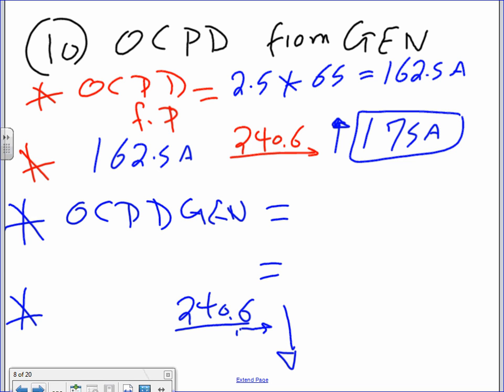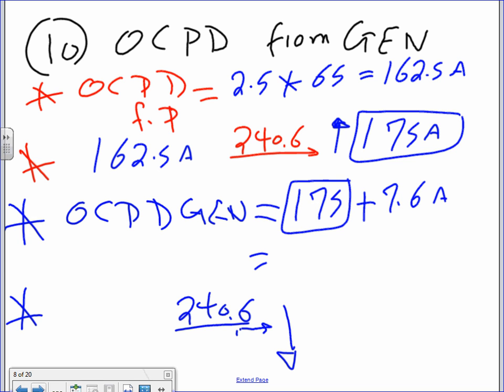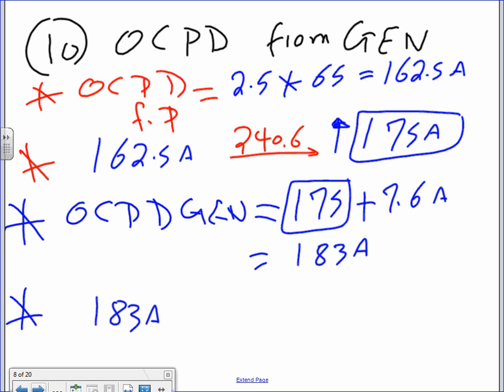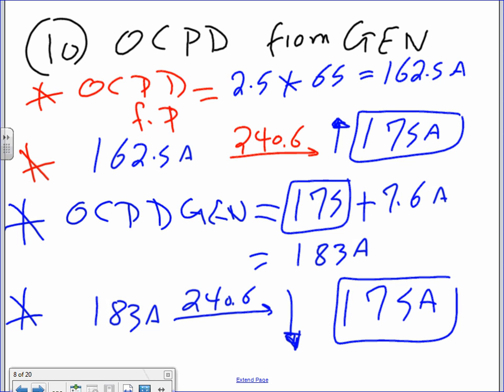Then, overcurrent protection device, guys, from the generator, the way you need to do it, you take the 175 amp that we just got. If you look at 7.6 amp, what's the 7.6 amp? That's the jockey pump amps. Add it to it, that will get you 183 amps. And then take the 183 amps, 240.6, go down. If it's not a standard, you go down. Okay, what's the next standard down? 175 anyway. So we went back to 175. Cool? So from the generator side, Derek, the circuit breaker is 175.